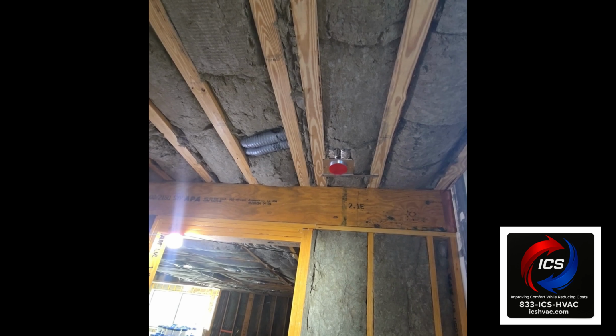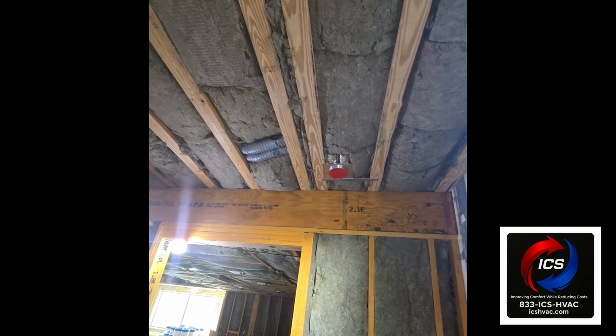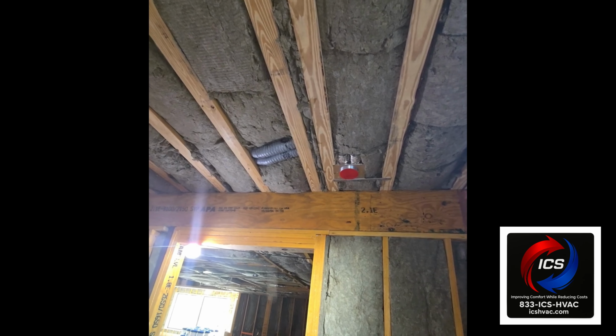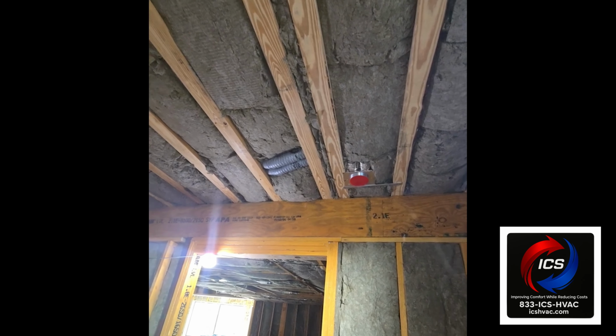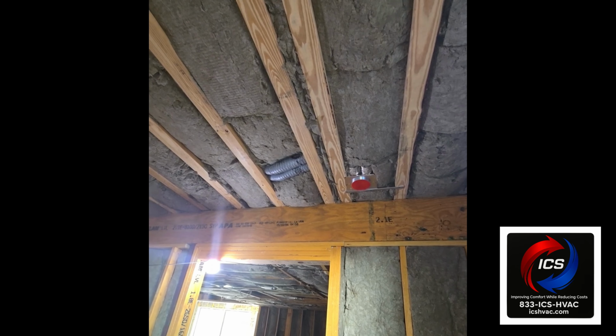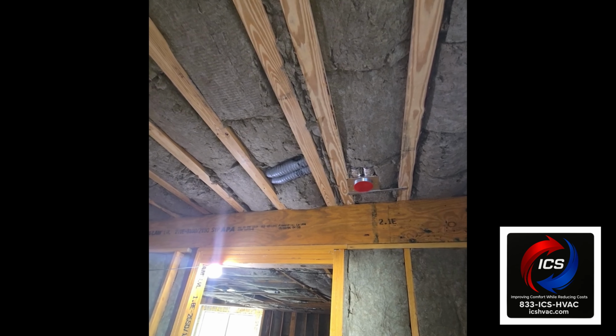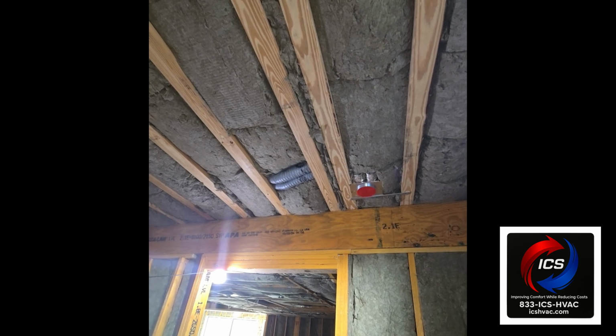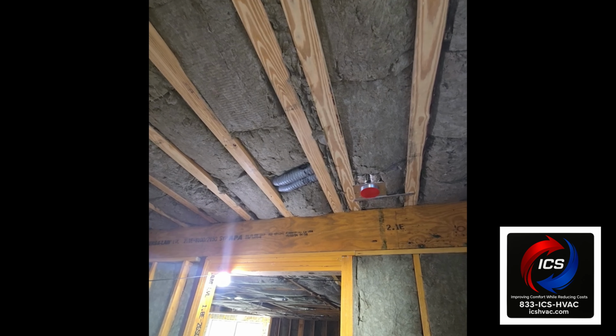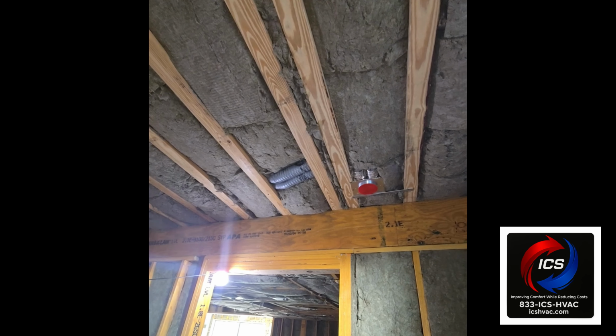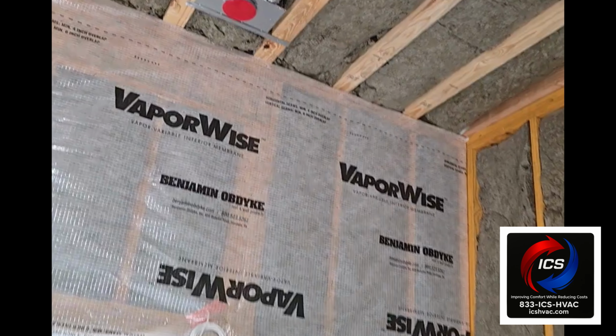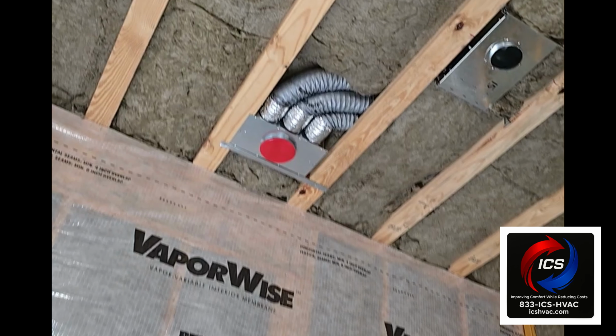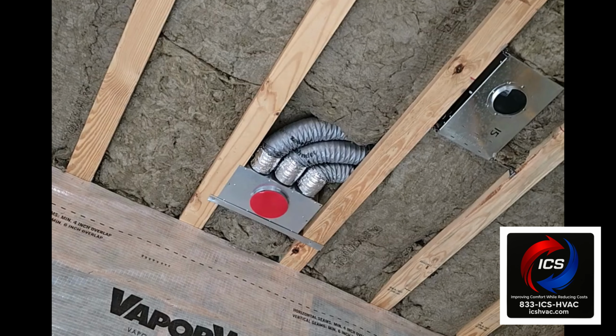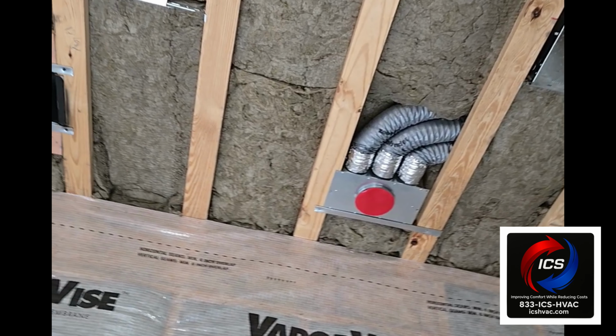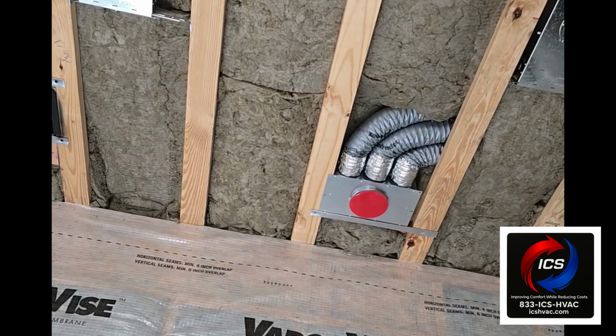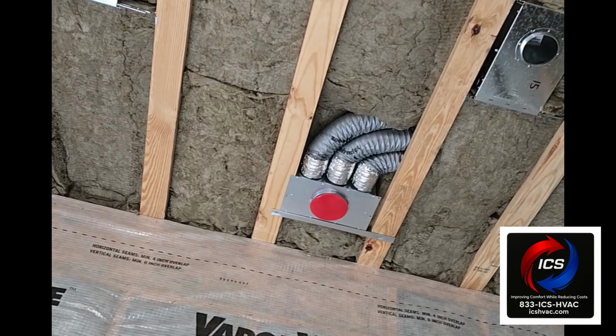I noticed there's 2 flexes there. So this is both supplying and exhausting? What's it doing exactly? It's both supplying. Each flex can only carry 15 or 20 CFM, so we're trying to achieve more than that. Zehnder has boxes with 2, 3, 4, 5 connections that make that possible. That makes sense, because I see some only have 1 supply and some have 2, so that's just more air into the spot, based on design.